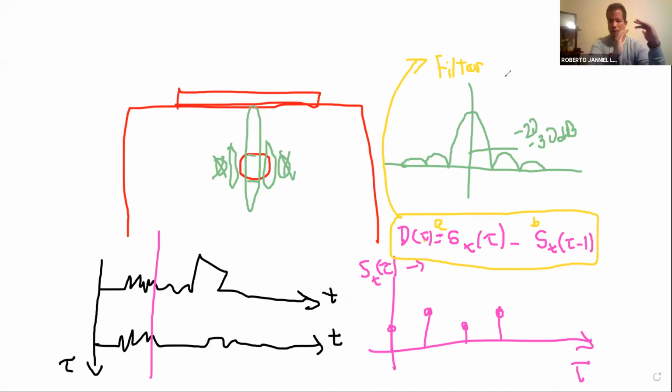The low frequency part, the slowly changing components of that signal, we're assuming comes from surrounding tissues. And we don't want it in our analysis. So we're filtering them out and we're only keeping the high pass part of it, which is the one that carries information about things that are moving faster.